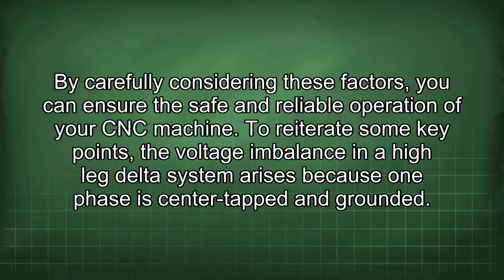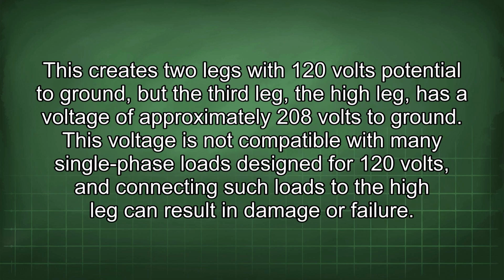To reiterate some key points, the voltage imbalance in a high-leg delta system arises because one phase is center tapped and grounded. This creates two legs with 120 volts potential to ground, but the third leg, the high leg, has a voltage of approximately 208 volts to ground. This voltage is not compatible with many single-phase loads designed for 120 volts, and connecting such loads to the high leg can result in damage or failure.